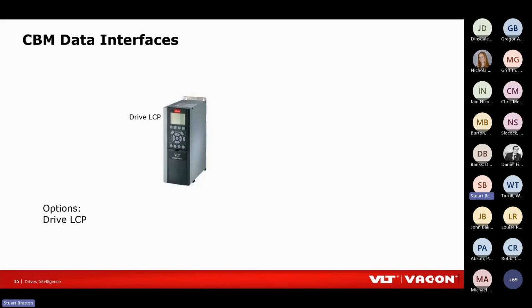So I said I would talk about the possible interfaces to CBM. The most basic interface is the keypad on the drive. You don't have to do anything with this at all if you don't want to, other than get a notification through the keypad. It will throw up a warning or an alarm and display that on the screen. Probably most people aren't going to just do that. We live in a more modern world than just wandering around looking at drive keypads.